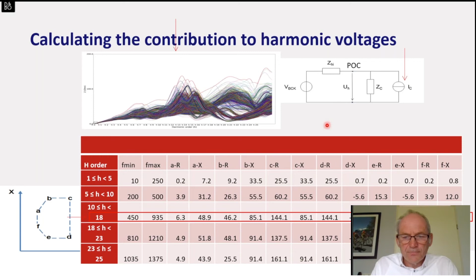That's for high voltage, but also for medium voltage and for low voltage a calculation has to be done, though not in as detailed a way as for the high voltage, because when we look to the medium voltage network and the low voltage network, there are millions of customers connected to the network, and you cannot look at every customer, what he is injecting and whether he is complying with the standard or not. So there has to be some research on what is, in the end, possible for harmonic injection, not depending on impedances, but just a simple table. What is possible? How could a single customer inject harmonic currents into the network?